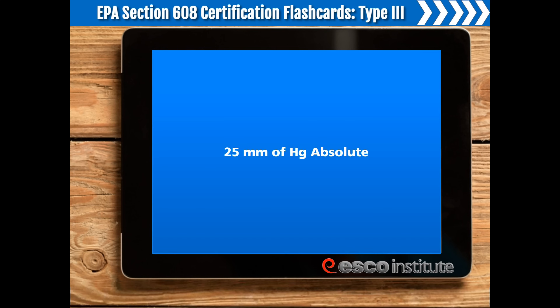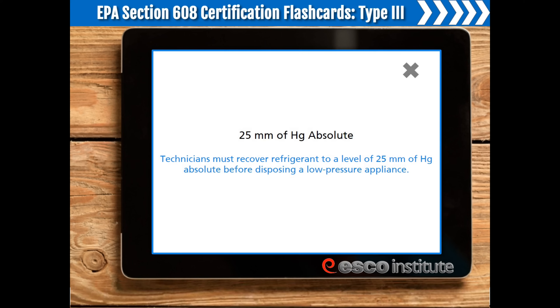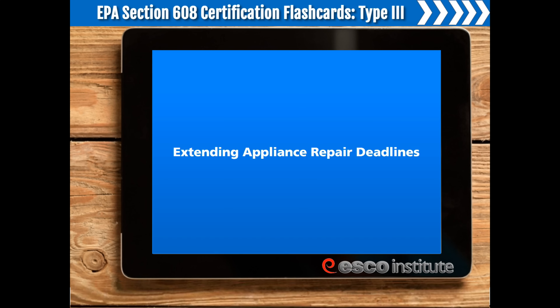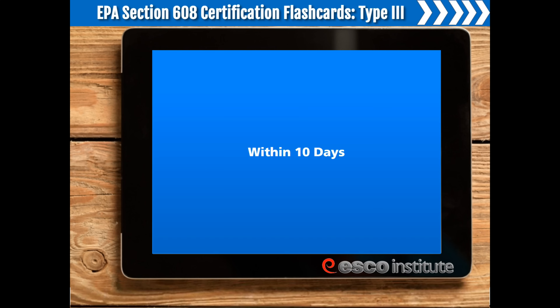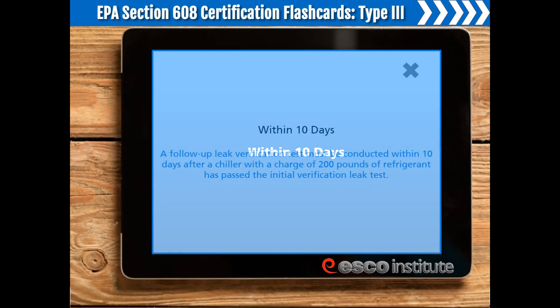25 mm of mercury absolute. Technicians must recover refrigerant to a level of 25 mm of mercury absolute before disposing of a low-pressure appliance. Extending appliance repair deadlines. A certified service technician not being available cannot be used as a reason to extend the appliance repair deadlines. Within 10 days. A follow-up leak verification test must be conducted within 10 days after a chiller with a charge of 200 pounds of refrigerant has passed the initial verification leak test.